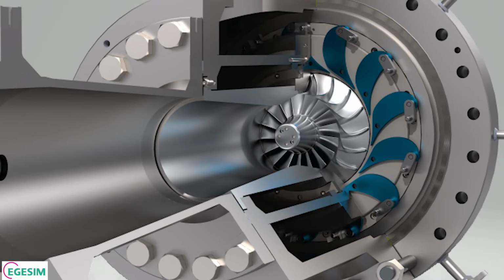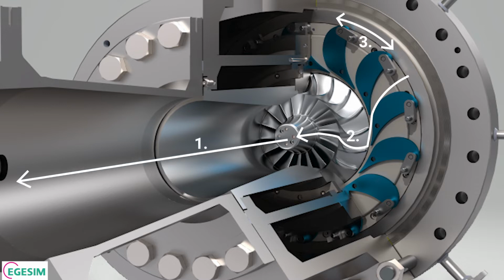Let us take a closer look at the inlet guide vane mechanism itself. You can see here that in blue, these are what we call the inlet guide vanes or the blades. These blades are movable, they are located on a pivot pin, and they can all be simultaneously rotated by the outer ring. They will accelerate the high pressure gas towards the impeller wheel, where it's giving up its power as rotational energy to the pinion and the gearbox, and the low pressure gas is then discharged via the discharge cone on the left hand side. So all blades move at the same time.